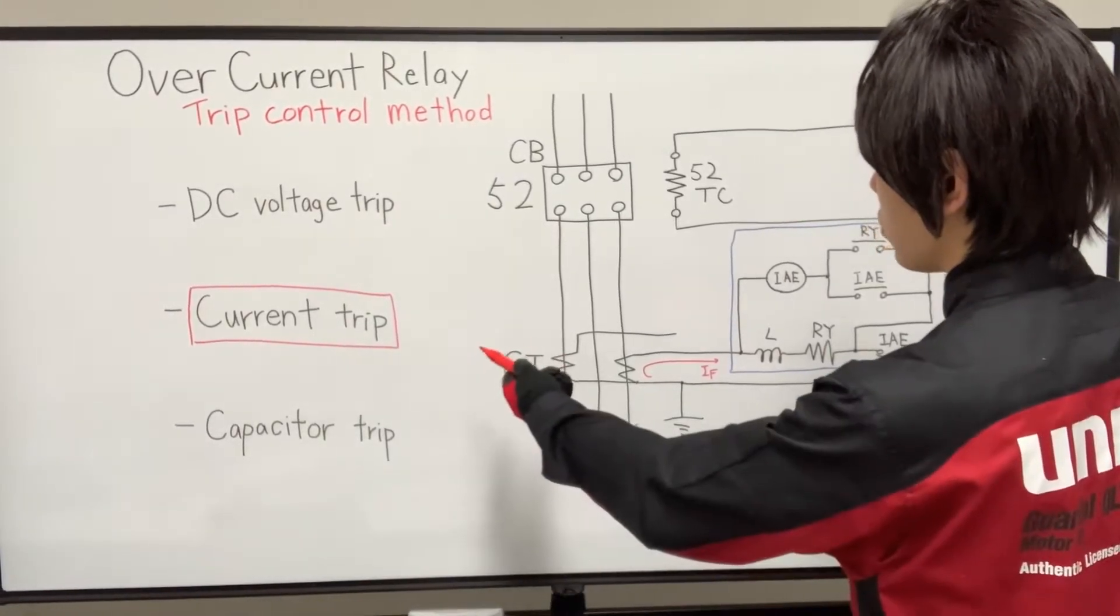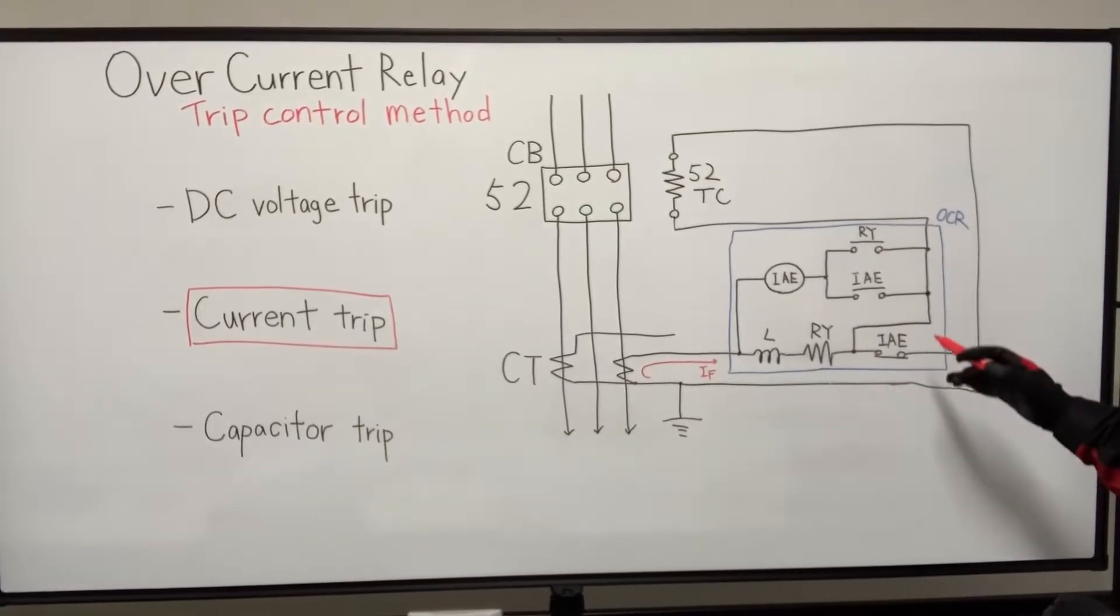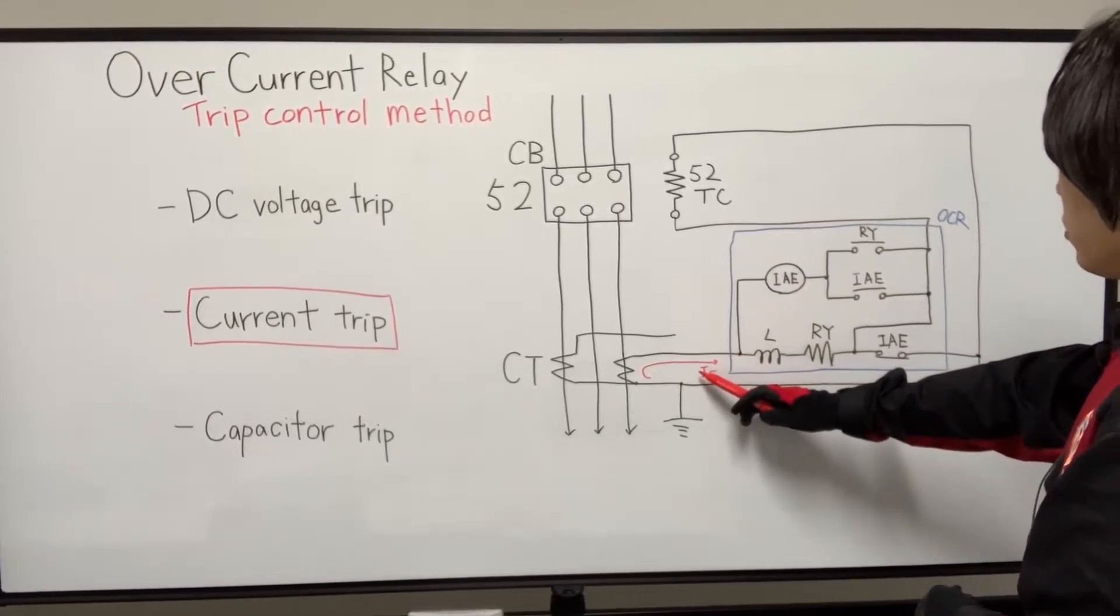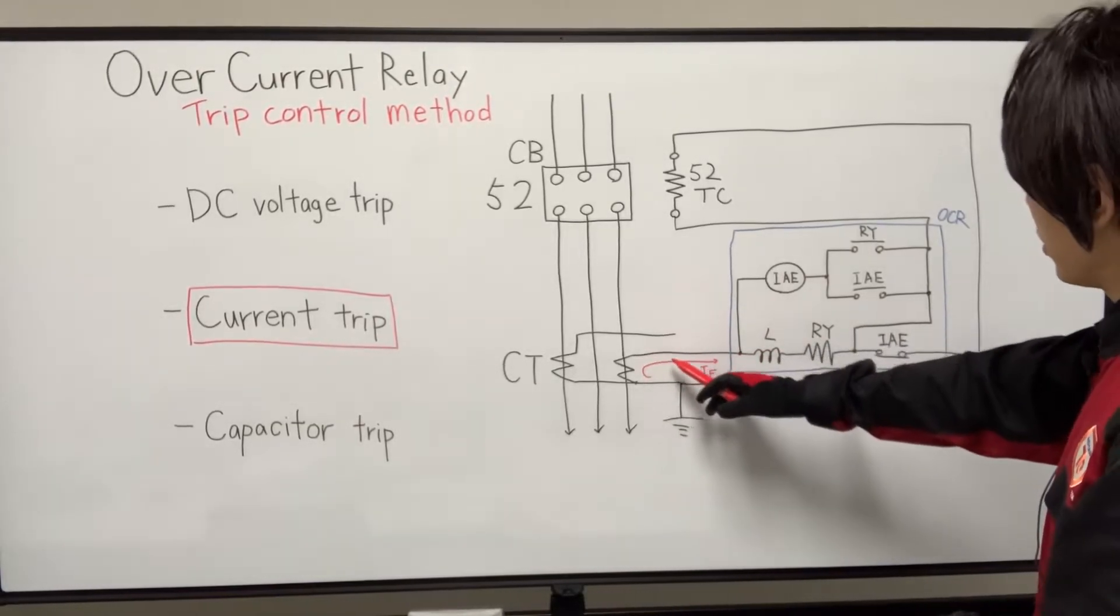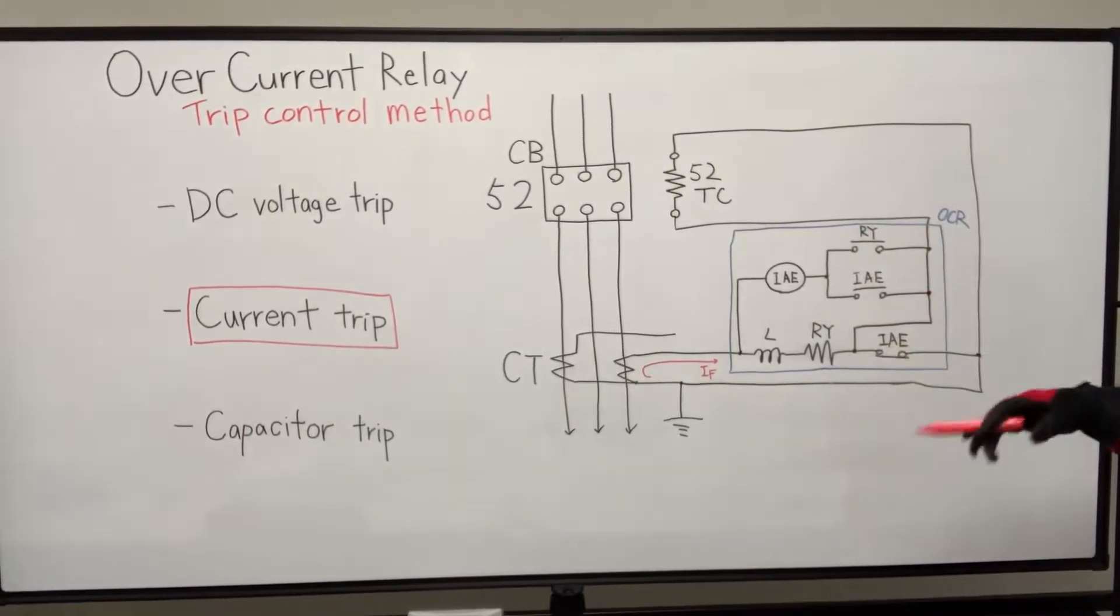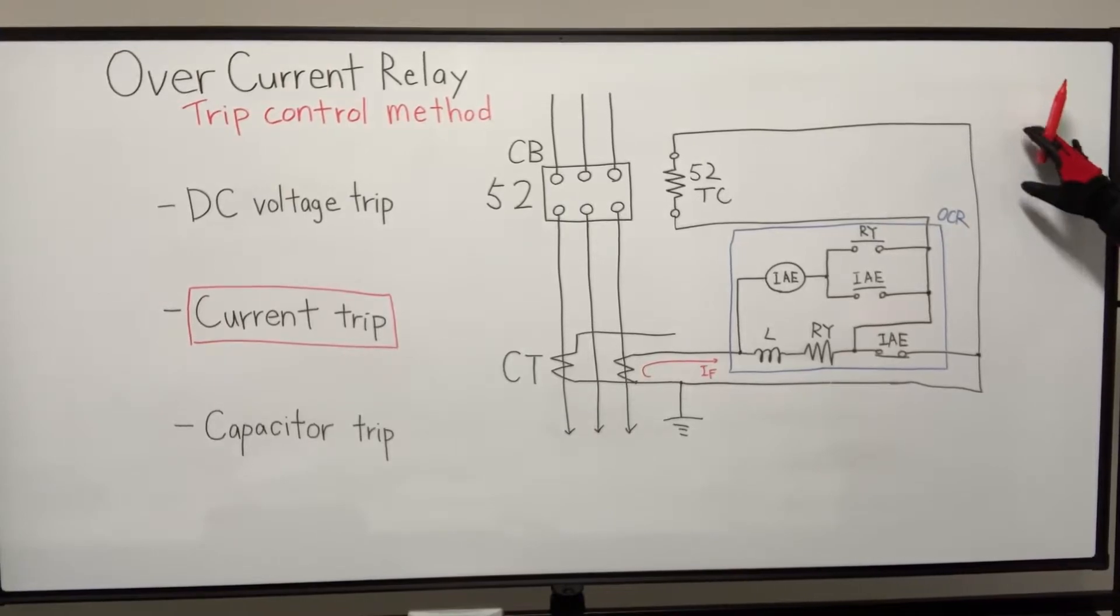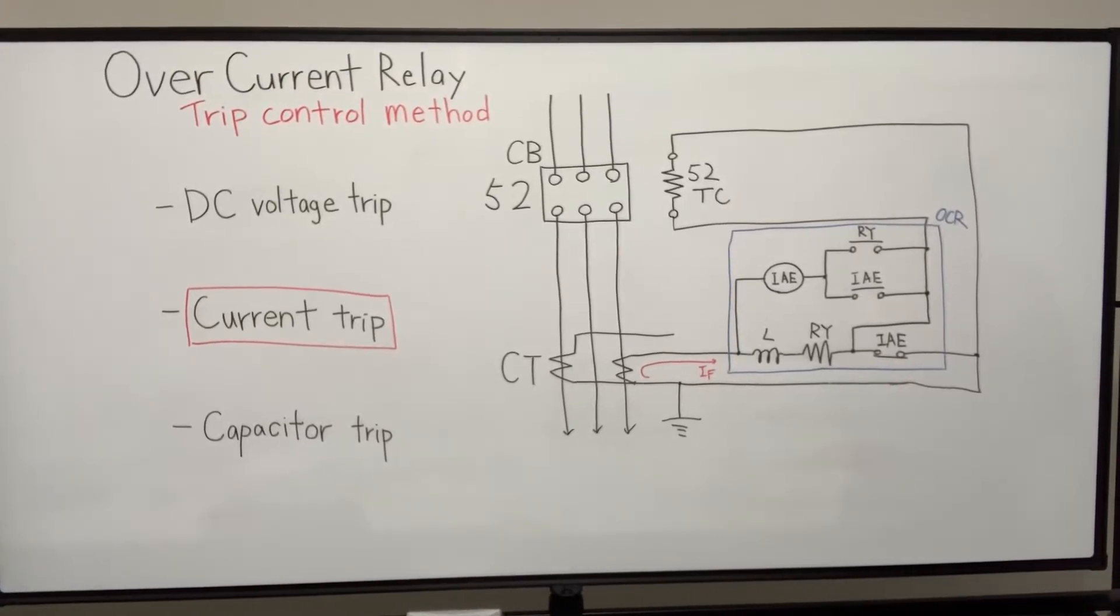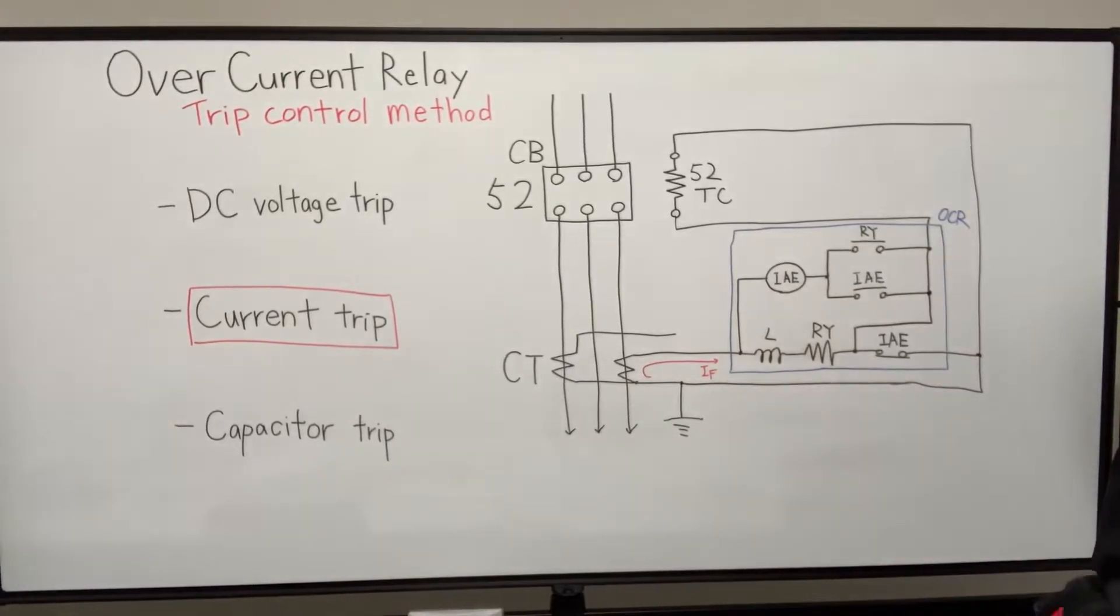The current trip method. In this method, the trigger for the trip is the current which is flowing in the CT's secondary side itself. So this method don't require any extra external power supply, like DC supply or something. They use the secondary side current itself.